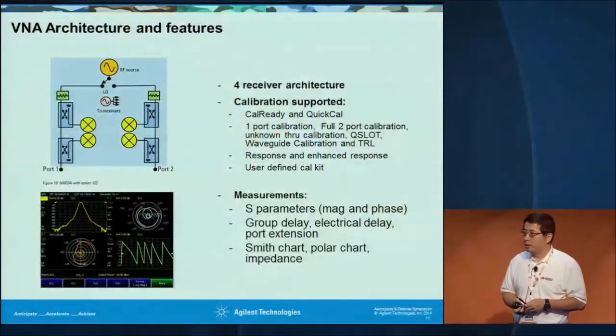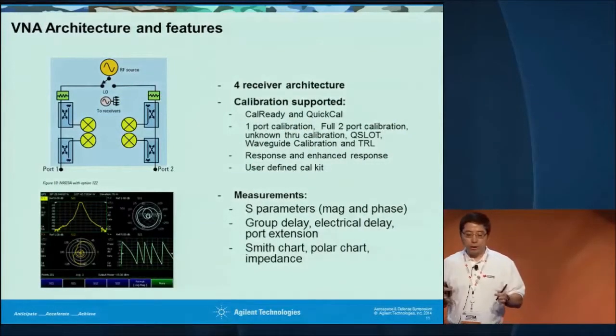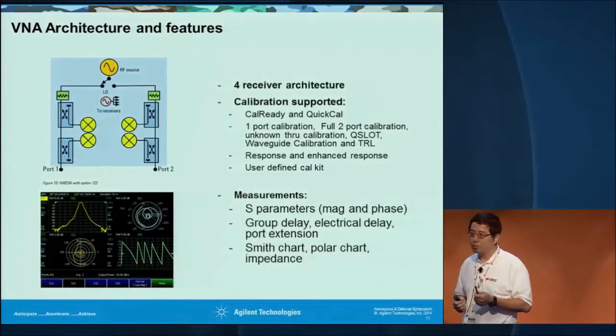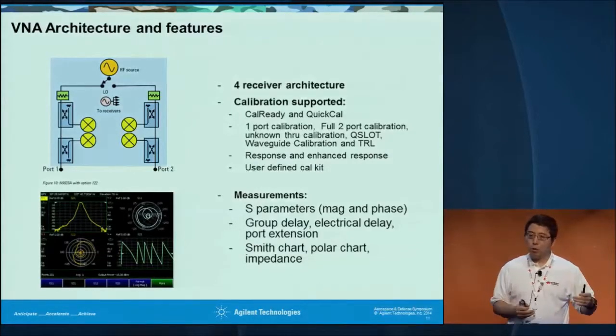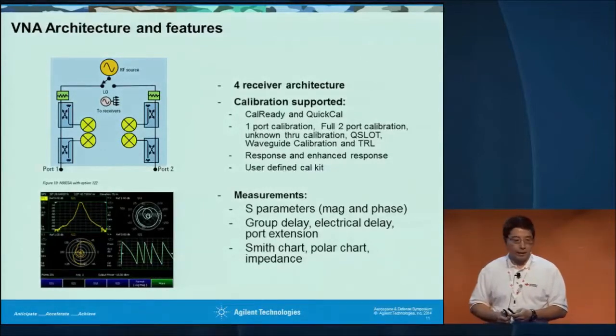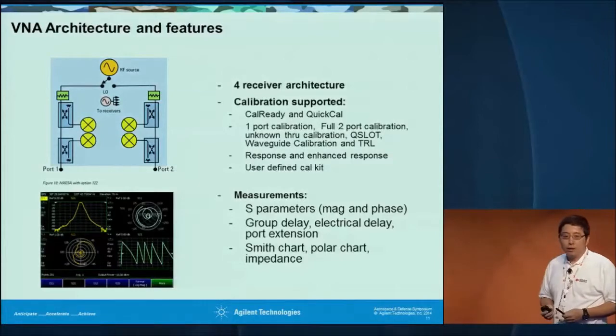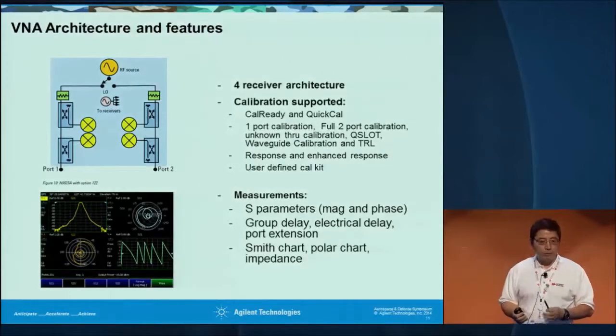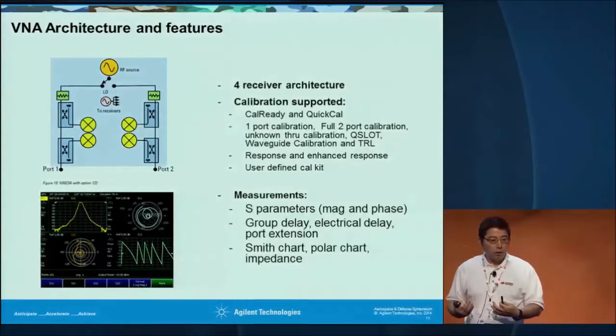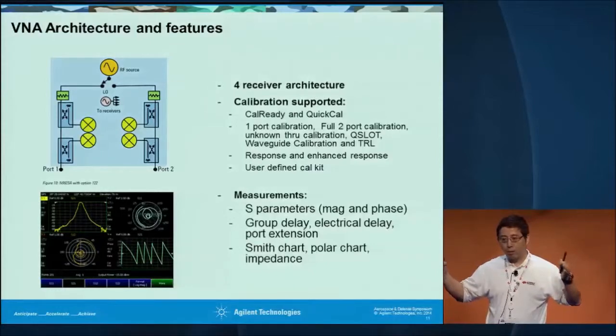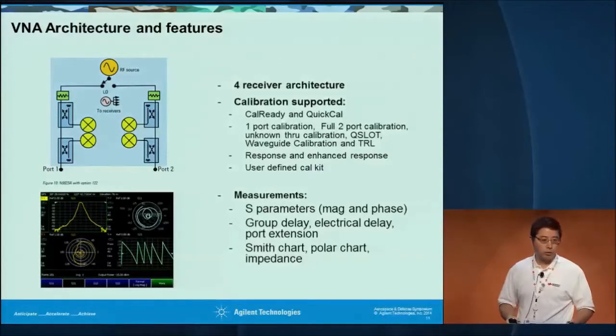There are a lot of components inside a communication system, especially cavity filters and amplifiers, so inevitably you're going to need a vector network analyzer to make those measurements. One thing that's unique about critical communication systems is that a lot of the devices are what we call non-insertable — you could have female-in, female-out, or even worse, a waveguide at one end and coax at the other. A traditional analyzer may not be able to handle that if it doesn't have a four receiver architecture. Forward receiver architecture allows us to calibrate the instrument using unknown-through calibration — meaning regardless of what type of connector you have, whether insertable or non-insertable, we'll be able to make those measurements.